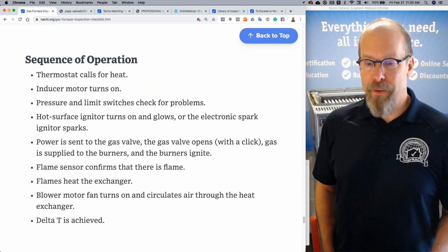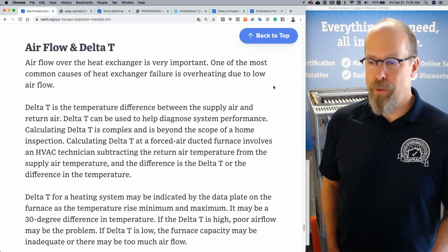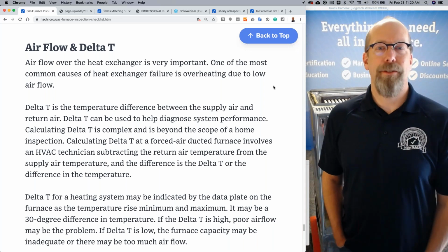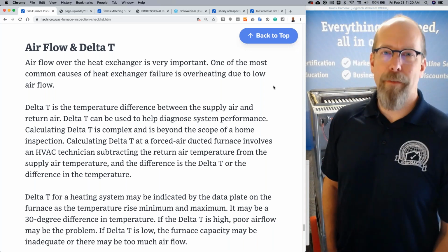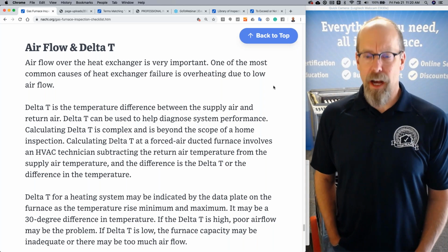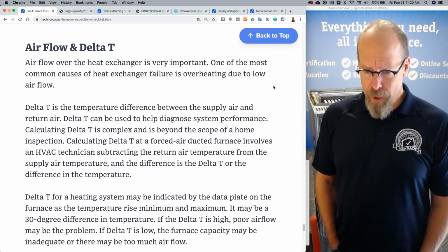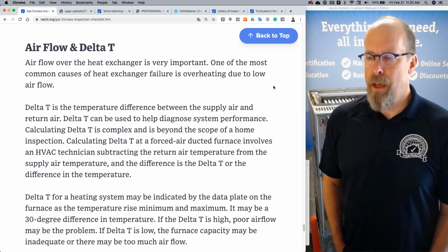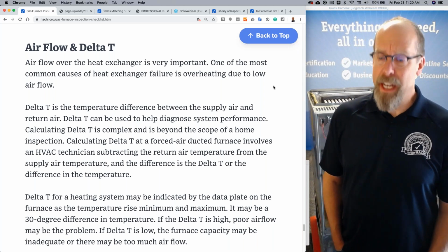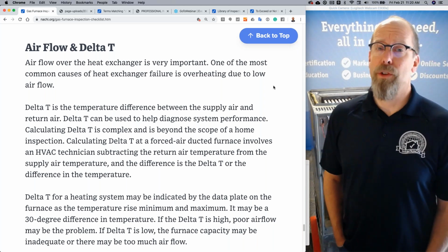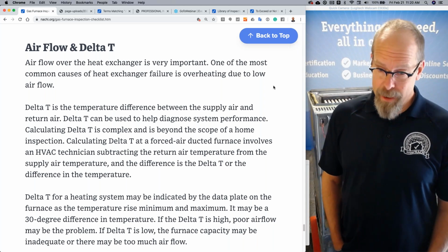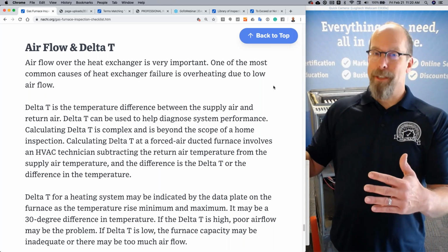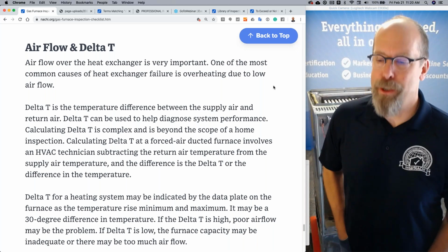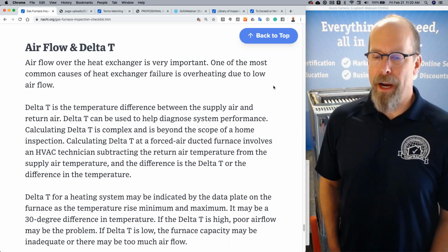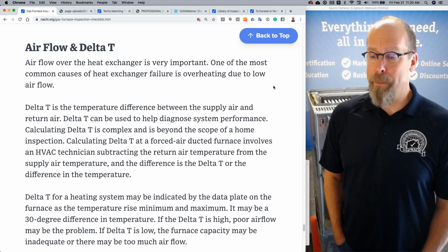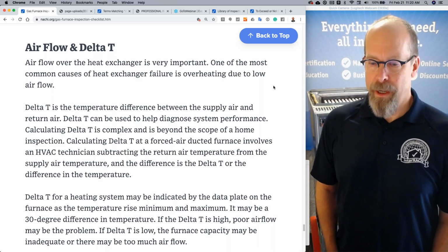We went over the sequence of operation, so we'll skip that. I think the last section in this checklist is a little information about airflow and delta T and how they're related. Airflow over the heat exchanger is very important. One of the most common causes of heat exchanger failure is overheating due to low airflow. Delta T, and this is way beyond the standards of practice again, is the temperature difference between the air supply and the return air. Delta T can be used to help diagnose system performance.